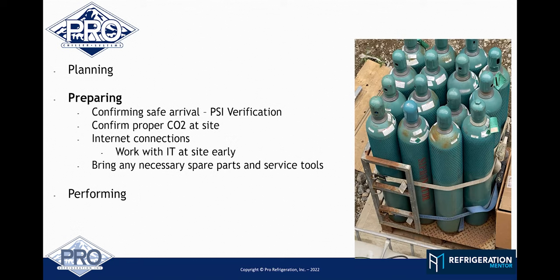That's important, because we don't want to go into a system that's below those critical points and feed in liquid—we don't want to create dry ice inside the system. So what I like to do is bring the whole system up after we've put a vacuum on it and evacuated everything. Then I bring the system up to 100 PSI—I know it doesn't have to be exactly 100, I think it's 67 or 73 PSI, but I like round numbers, so I just get it up to 100 PSI and then you're safe.